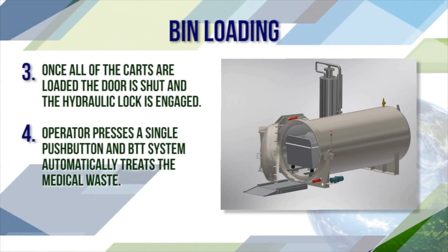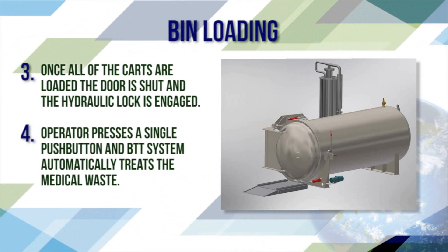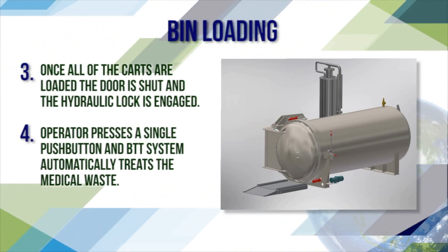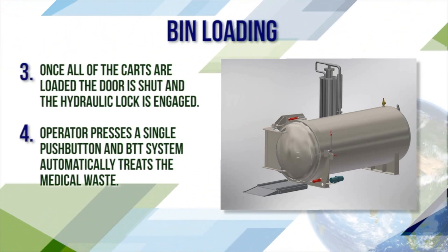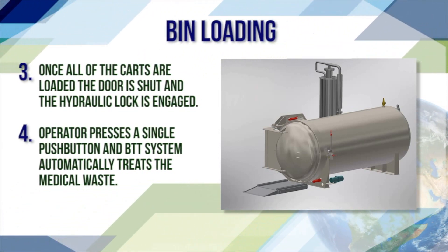Bin loading continues. Once all the carts are loaded, the door is shut and the hydraulic lock is engaged. Operators press a single button and the BTT system automatically treats the medical waste.